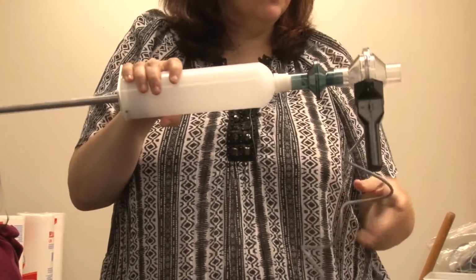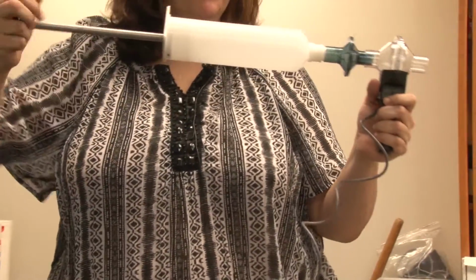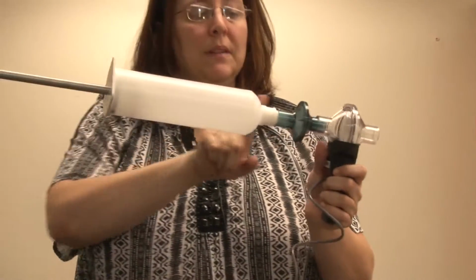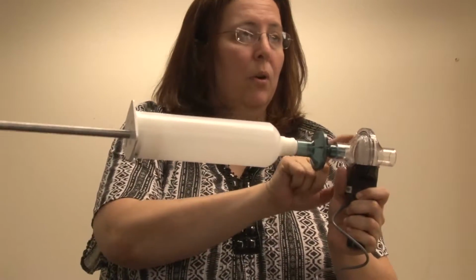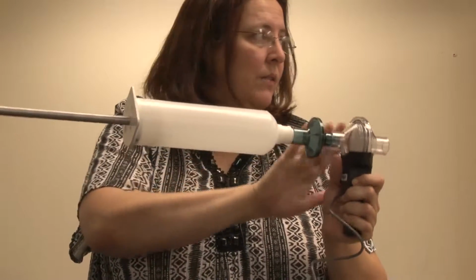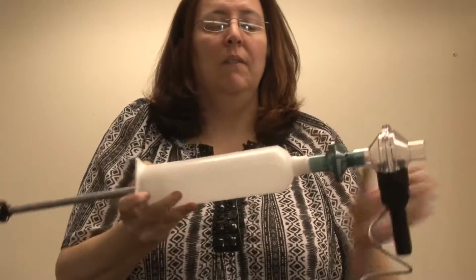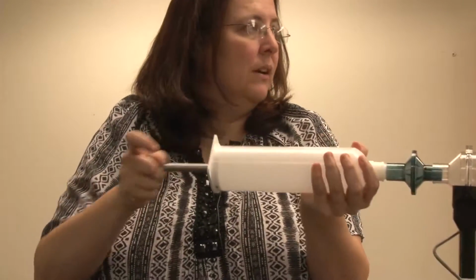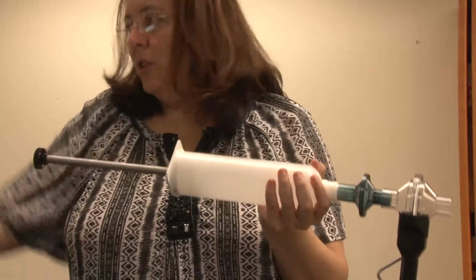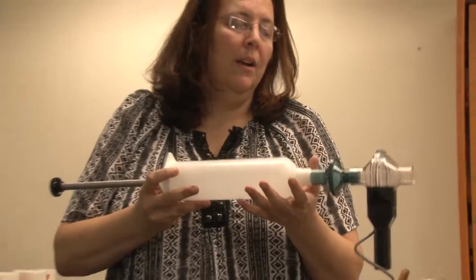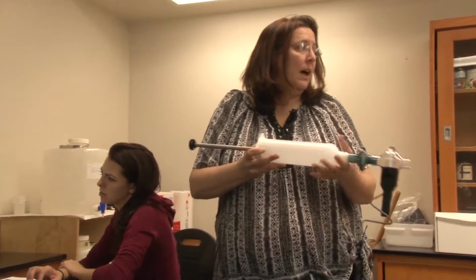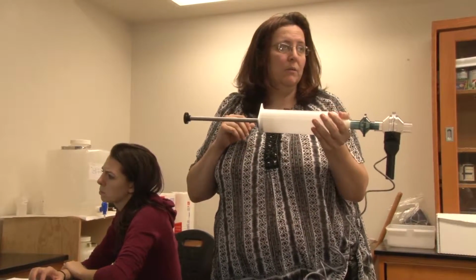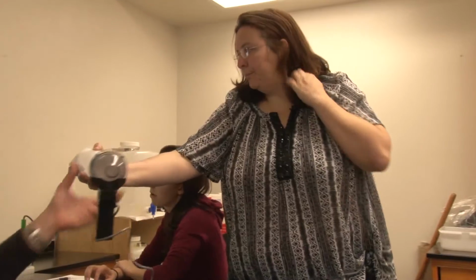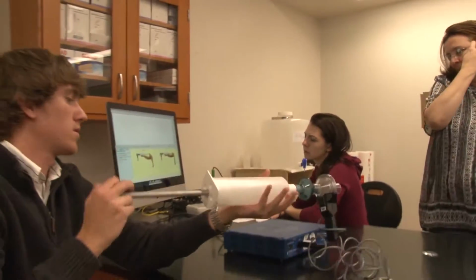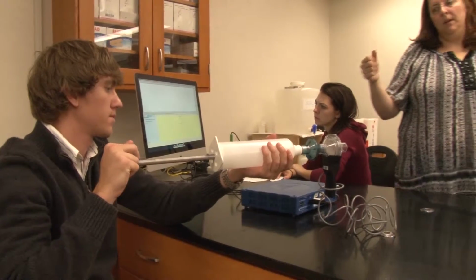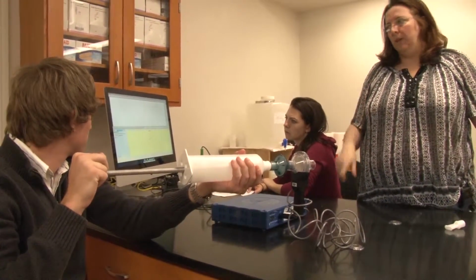The worst thing that the students can do, and you need to tell them this, is to hold on to the respirometer while they're pushing the plunger. Because what happens is that puts pressure on this part of the equipment, and it will crack this part where the screws are. This is a very expensive piece of equipment to replace. If they just hold the syringe and move the plunger like so, they're not going to break the equipment. And it shows that in the picture. And it also says it in the lab manual. But demonstrate it before the class. Just say, make sure when you're calibrating that you're holding onto the syringe. Okay? All right. So when she clicks calibrate, he's going to plunge it in and out 5 times with 2 seconds in between.